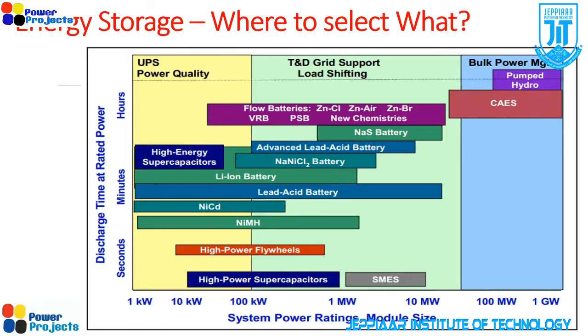So when we convert this other form of energy to electricity, at the same moment this electricity has to be converted into some other forms, like heat or rotational or fans, mechanical, whatever it is. Whenever there is a mismatch between this, then the key electrical parameter, which is frequency, will change. So it is necessary that we maintain the generation and demand constant each and every moment.